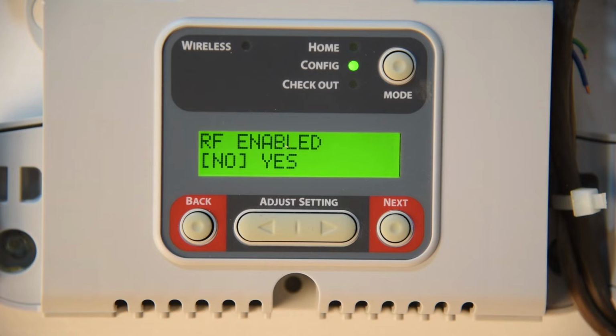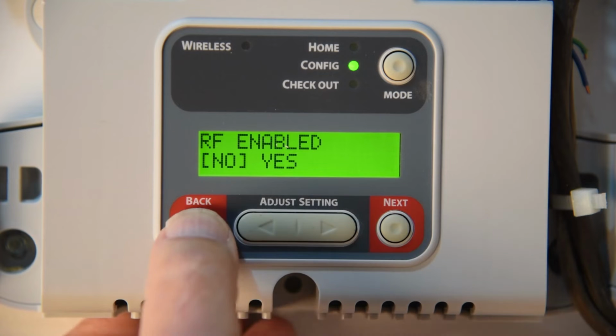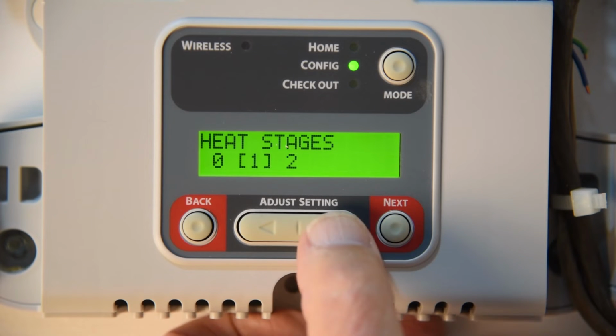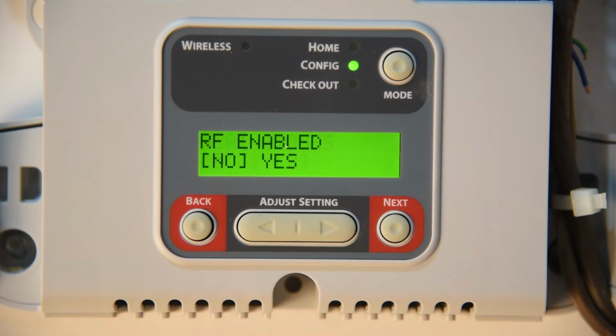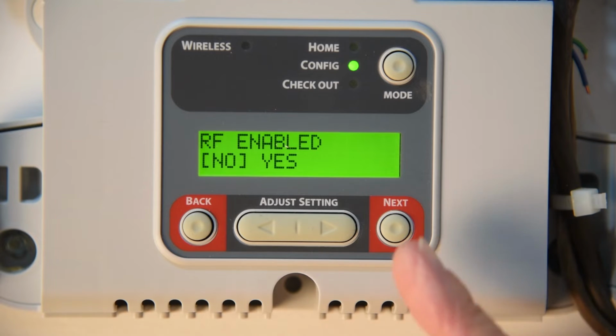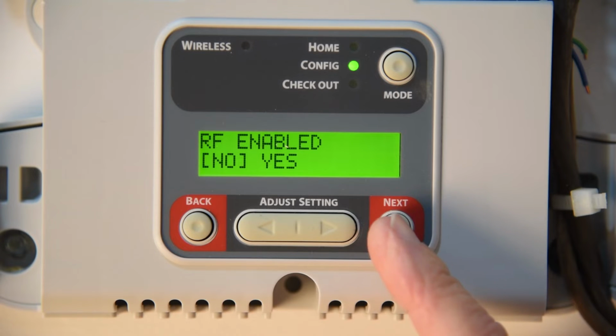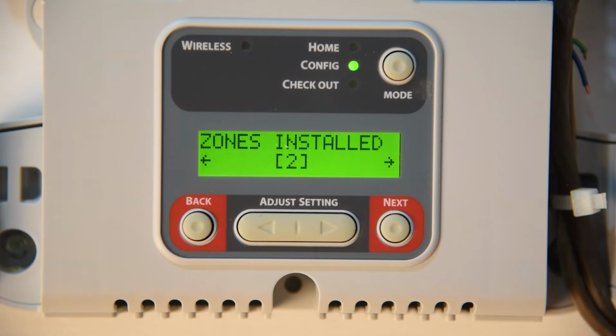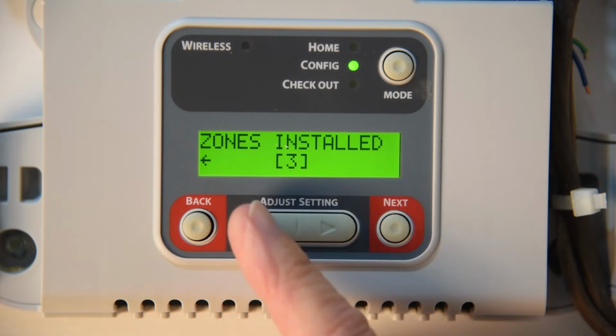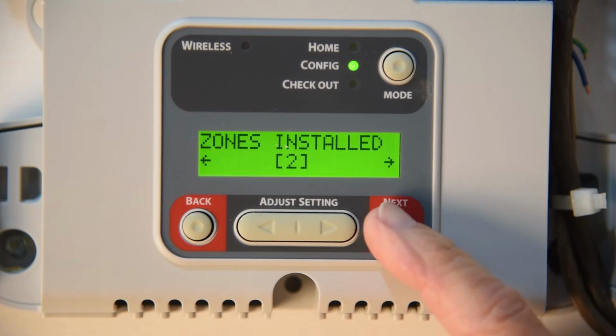And then it comes to the RF enabled. Well, I really have 2, so I'm going to go back and change that to 2. So I'm going to hit next. RF enabled. I do not have RF. That's if you're using a wireless thermostat. If you say yes, then you're going to have other questions to answer to tie your thermostats into the unit. I'm going to hit yes or no, and I'm going to hit next. Zones installed. Well, you can have 1 zone, 2 zones, or 3 zones. In my case, I have 2 zones. I'm going to hit next.